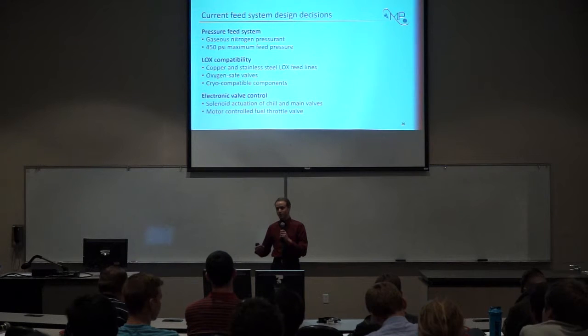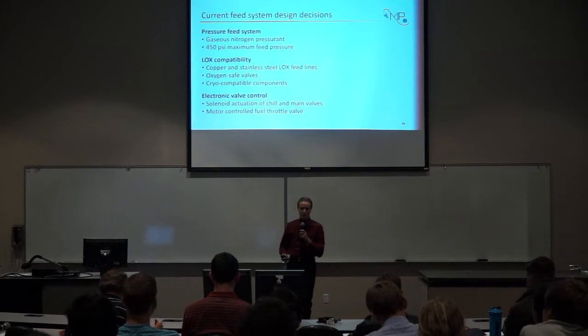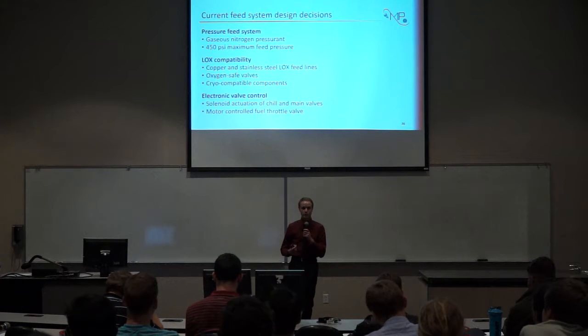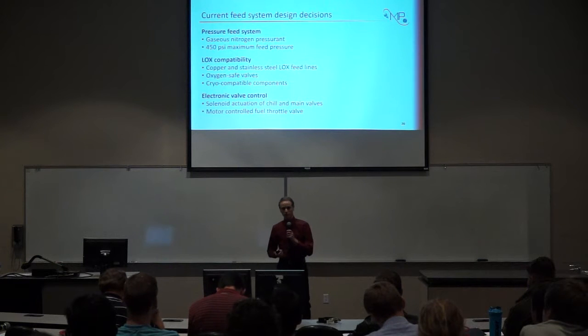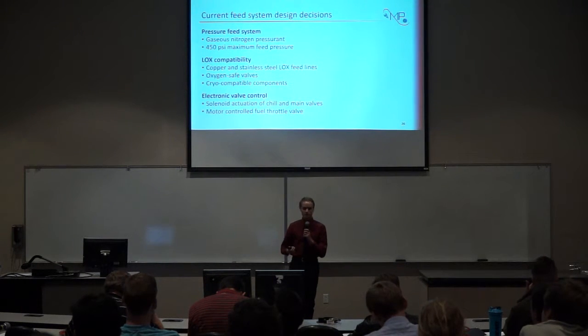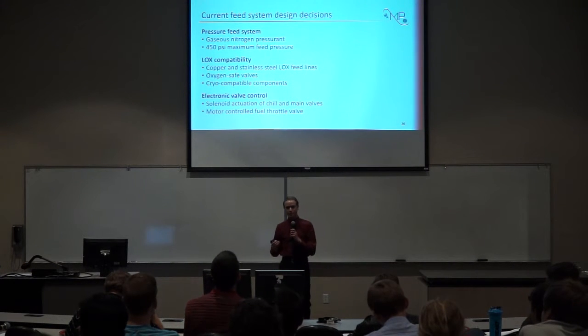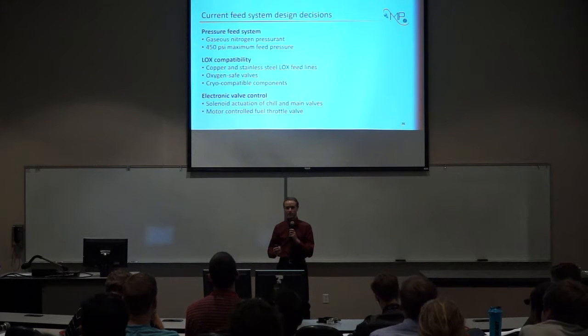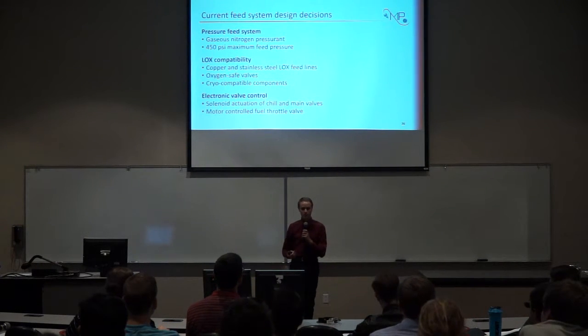Additionally, because we are working with liquid oxygen, at least the LOX half of our feed system will need to be LOX compatible, meaning it's made out of materials which will not react with LOX while in contact with it. With that in mind, we're going to utilize copper and stainless steel components throughout the LOX side of the feed system. We will also be selecting all valves for that side of the system to be oxygen safe, meaning the metals they're made of, as well as any lubricants or packing materials used, will not react with the liquid oxygen. It also needs to be cryocompatible and able to function at the cryogenic temperatures of liquid oxygen.